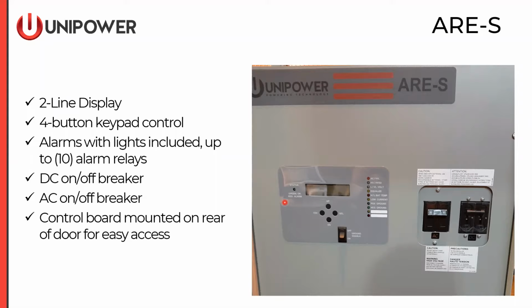So we open the door. If a main controller needs to be replaced, simply open the door, remove 4 screws, and replace the control board. You'll notice also just below the 4-button keypad, all ARE-S's are always equipped with this ground fault disable switch. It's an option. It remains an option still on the ARE-M, but we decided to always deploy the switch with the ARE-S. Just kept things simpler. Next slide, please.